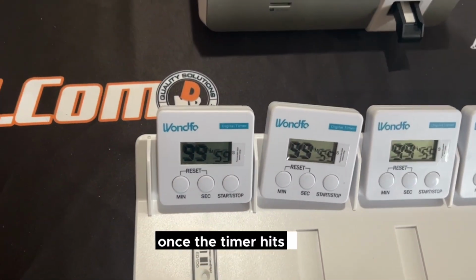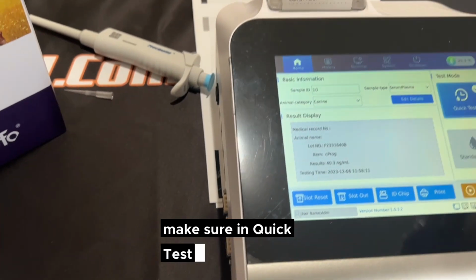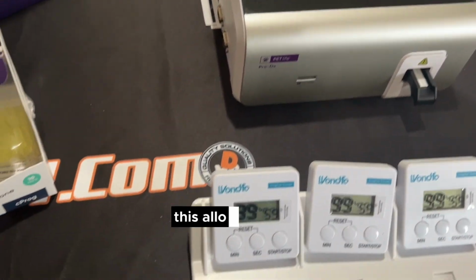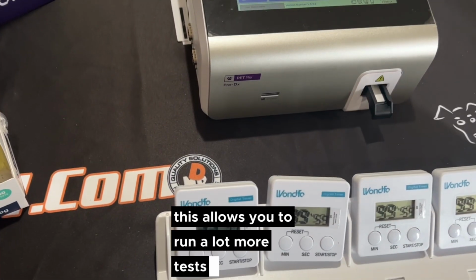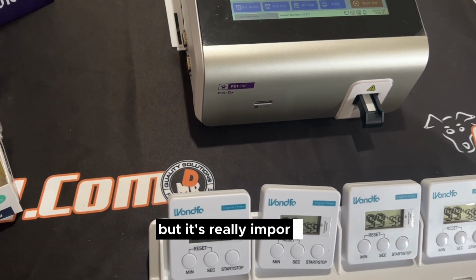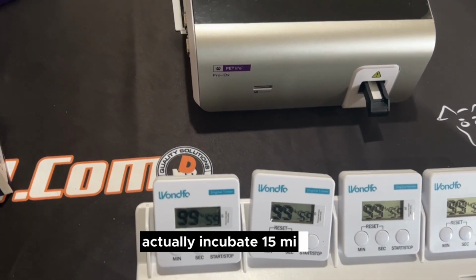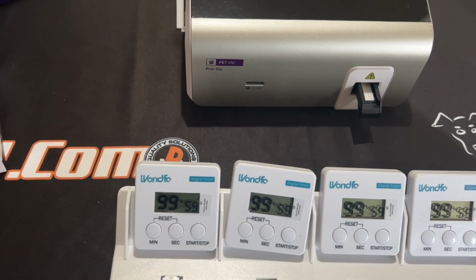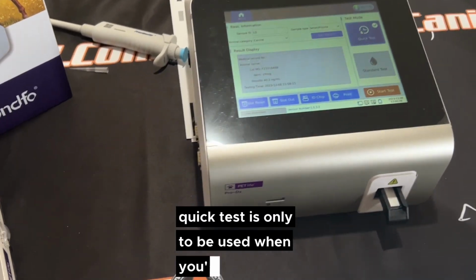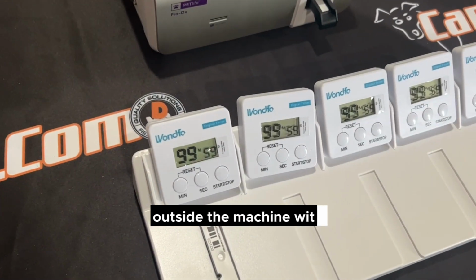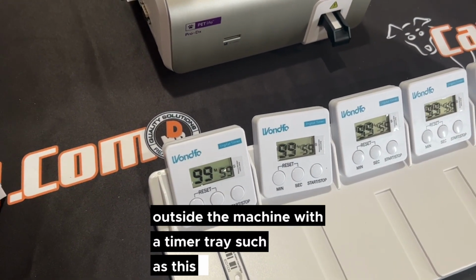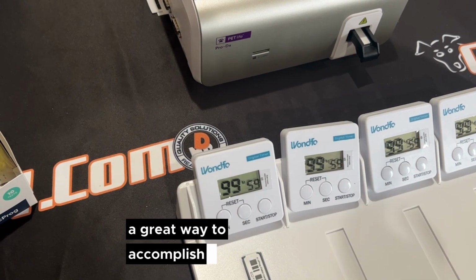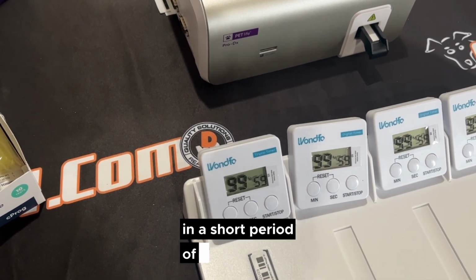Once the timer hits 0, make sure you're in quick test and start the test. This allows you to run a lot more tests much quicker, but it's really important that the tests actually incubate for 15 minutes. So you cannot skip the 15 minutes. Quick test is only to be used when you're incubating outside of the machine with a timer tray such as this. A great way to accomplish much more testing in a short period of time.